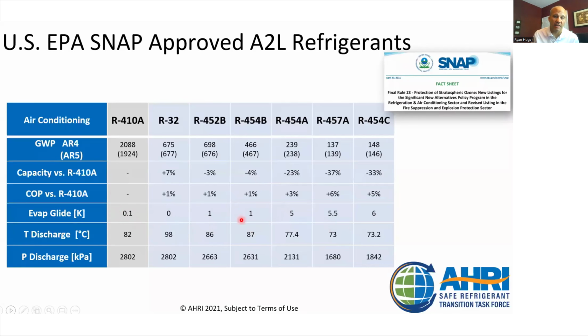1 degree of Kelvin glide is not enough that anyone would notice. And if it did leak out at that exact point in the evaporator and then you did fix it and top it off, and your percentage was a little bit off on the mix of the two, it is so minor it would not matter. And if you had so much leak out that it mattered, well, that means you're adding so much more back in to dilute it back down. So it's a non-issue. It's come up with a few people.